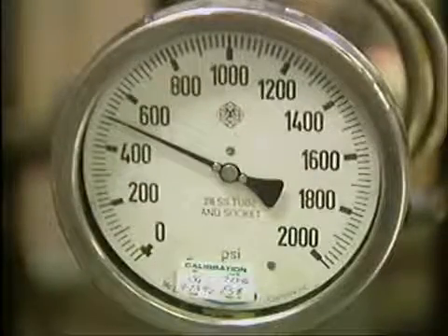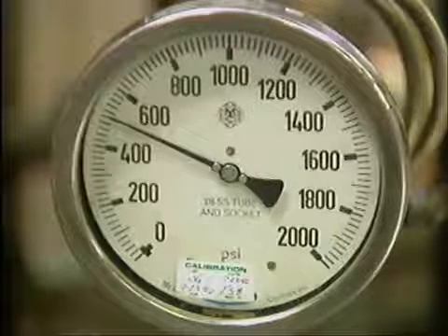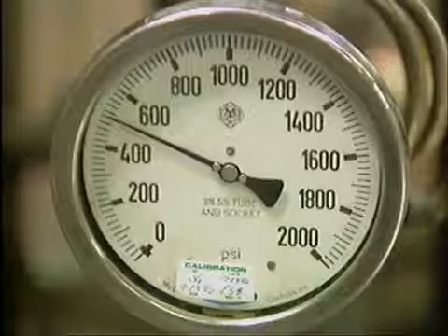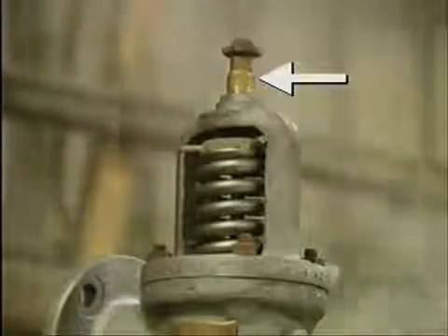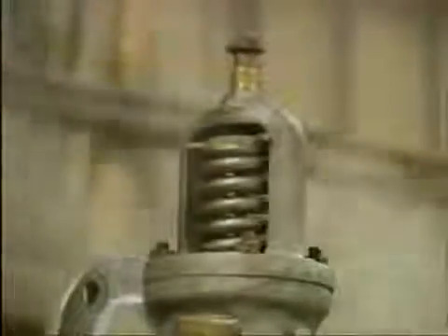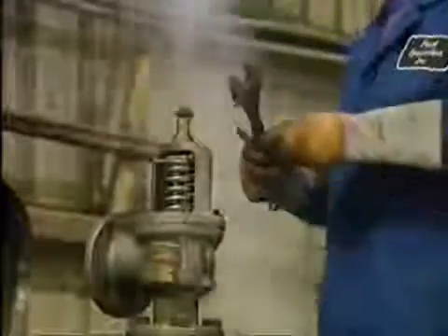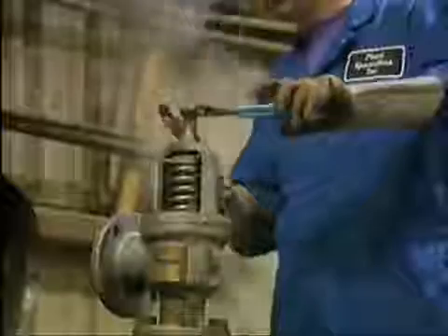In any case, when you're testing popping pressure, you're checking whether the valve opens when it's supposed to. If it opens too soon or too late in relation to the valve set point, you must make adjustments. For this huddling chamber safety valve, you make set point adjustments by turning the compression screw. But before you can do that, you must lower the pressure so that there's no chance of the valve opening accidentally while you're working on it. You must also break the lock nut free. If you try to turn the compression screw without loosening the lock nut, you'll probably damage the screw.